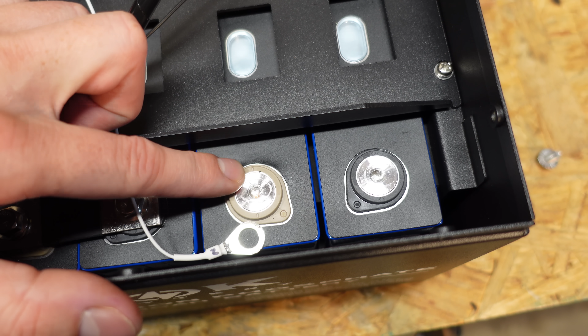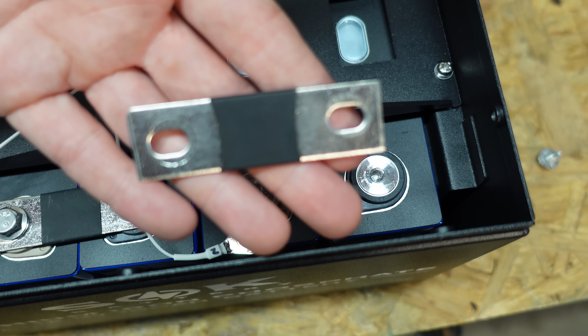With the first bus bar removed, we can see the tops, the terminals of the individual cells. They are very shiny, aluminum terminals. They don't appear to be scratched up or anything, so I know these are new cells, not used. The bus bars were held down with a 10mm hex bolt, and this is a serrated flange nut, which is good.